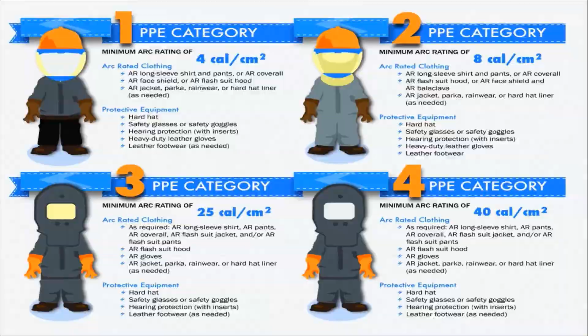You might have heard me say hazard risk category, also seen as the acronym HRC on clothing tags. What we see most of in industry is HRC2 and HRC4. You can see how they get into heavier clothing as you go through categories 1, 2, 3, and 4. You can also see the relationship — in category 2, the minimum arc rating is 8 calories per centimeter square, telling you what to wear. Same with 3 and 4. Categories 2 and 4 are what we see most. Categories 3 and 4 are commonly referred to as the beekeeper suits, and a 40 cal rating is what we see most in our marketplace.